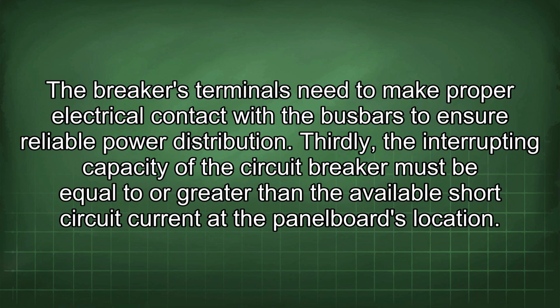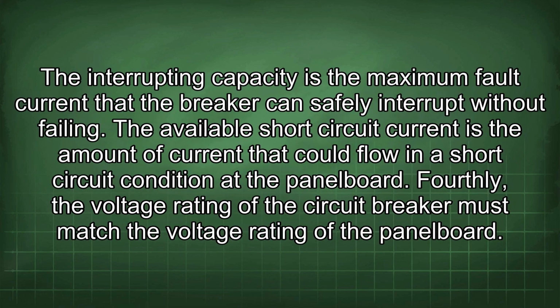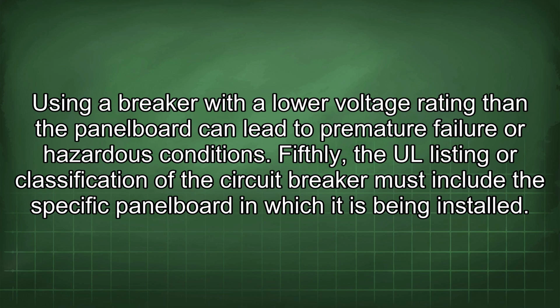Thirdly, the interrupting capacity of the circuit breaker must be equal to or greater than the available short circuit current at the panelboard's location. The interrupting capacity is the maximum fault current that the breaker can safely interrupt without failing. The available short circuit current is the amount of current that could flow in a short circuit condition at the panelboard. Fourthly, the voltage rating of the circuit breaker must match the voltage rating of the panelboard. Using a breaker with a lower voltage rating than the panelboard can lead to premature failure or hazardous conditions.